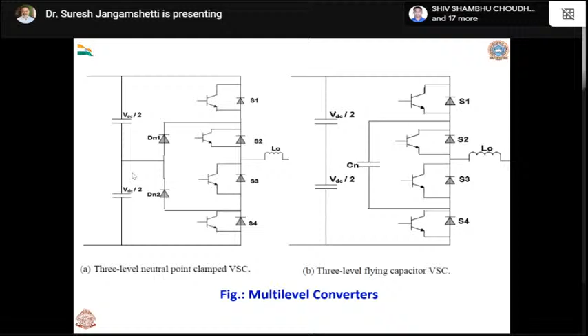Another important thing to keep in mind is that there will be a requirement of reactive power for the wind turbines. That is another major study complained about by many grid operators, saying that reactive power must always be balanced in any grid system. In grid connected AC grids, if anything is drawn or pumped in excess, it is going to cause instability. That also has to be kept in mind.